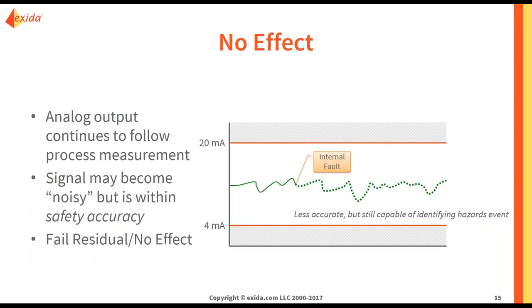The last failure mode is no effect. In this case, an internal failure would cause a less accurate or noisy output. The signal is still following the process value and it can identify a hazardous event, although it is less precise. We call this fail residual or no effect. This would not be applied to your PFD calculation. This can still respond to your hazardous scenario, so we would call it fail residual, no effect.